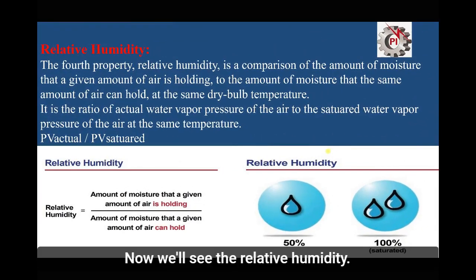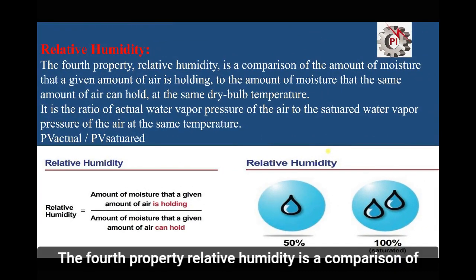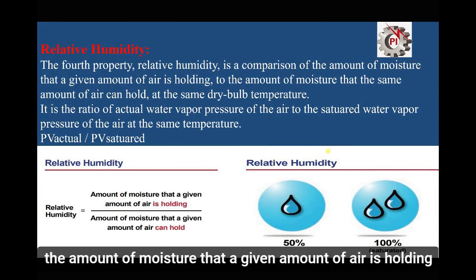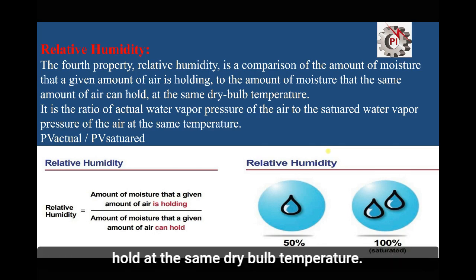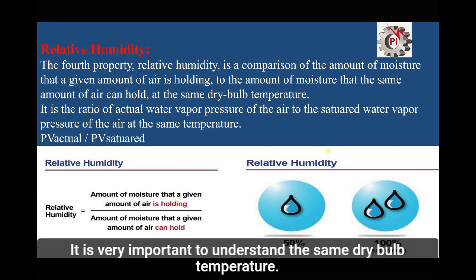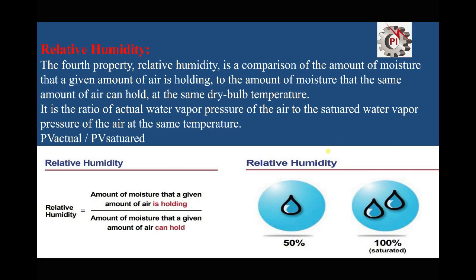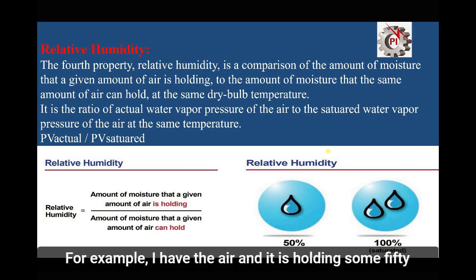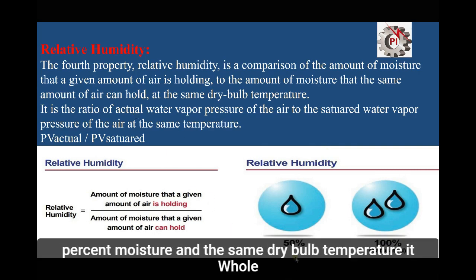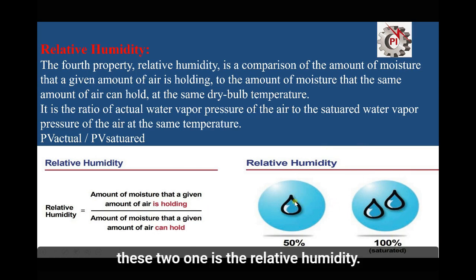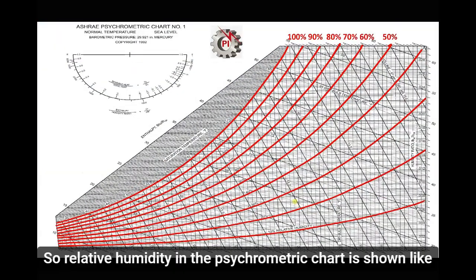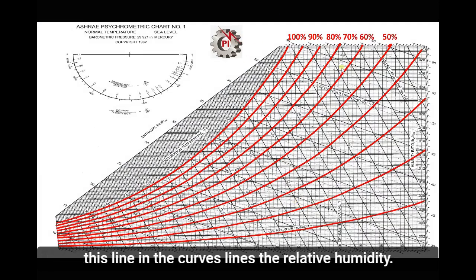The fourth property is relative humidity — the comparison of the amount of moisture a given amount of air is holding to the amount it can hold at the same dry bulb temperature. For example, if air holds 50% of the moisture it could hold at saturation, the relative humidity is 50%. In the psychrometric chart, relative humidity is shown as curved lines.